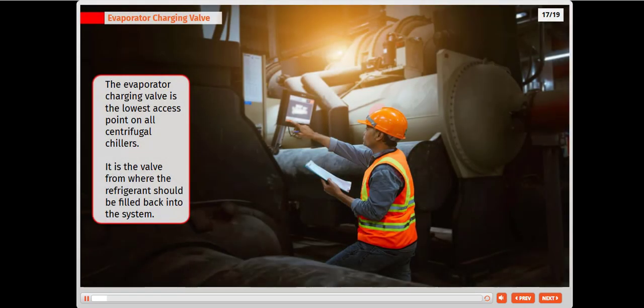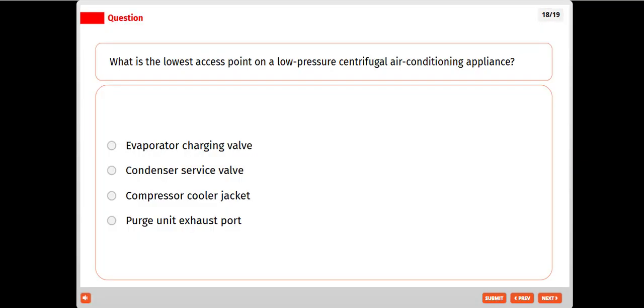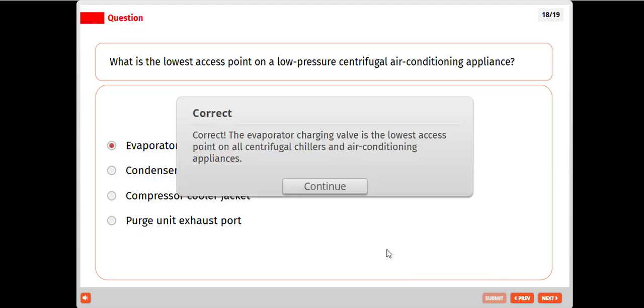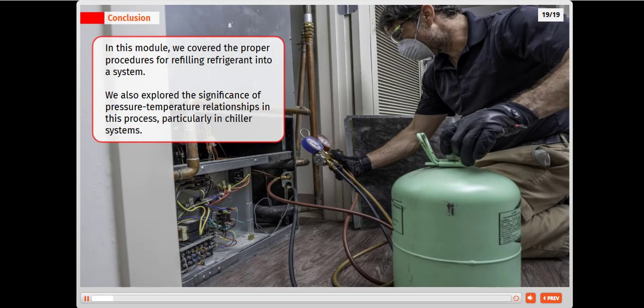The evaporator charging valve is the lowest access point on all centrifugal chillers. It is the valve from where the refrigerant should be filled back into the system. What is the lowest access point on low pressure centrifugal air conditioning appliances? Evaporator charging valve. In this module, we covered the proper procedures for refilling refrigerant into a system. We also explored the significance of pressure-temperature relationships in this process, particularly in chiller systems.